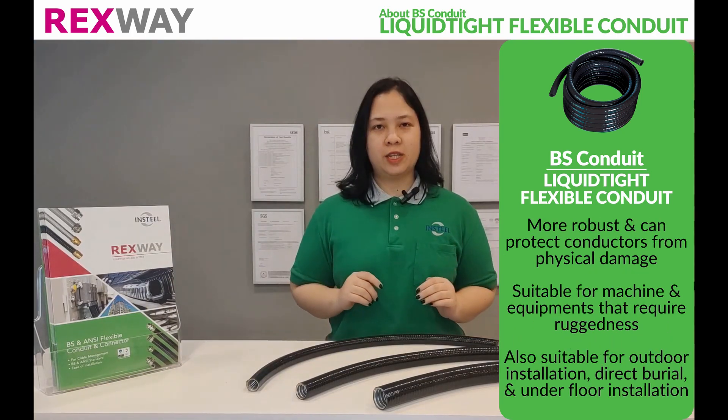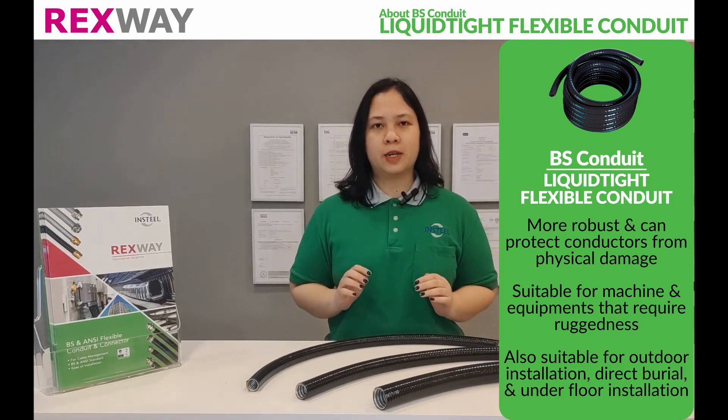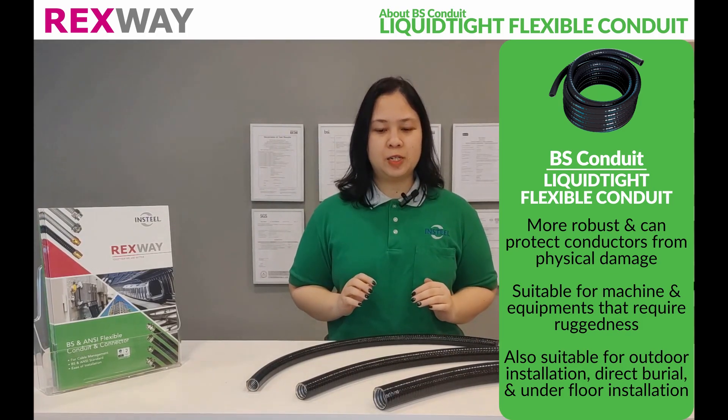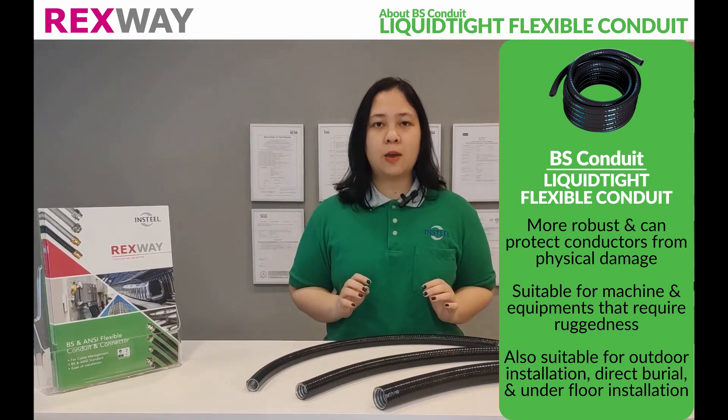Rexway BS Liquidtight Flexible Conduit is more robust and able to protect conductors from physical damage. This makes it suitable for machines and equipment that require ruggedness, such as presses, conveyors, and automated lines. It is also permitted for outdoor installations, direct burial, and underfloor applications.